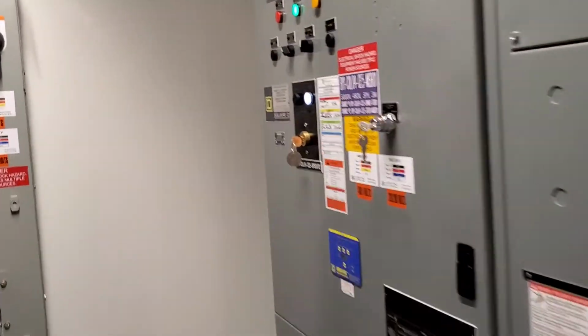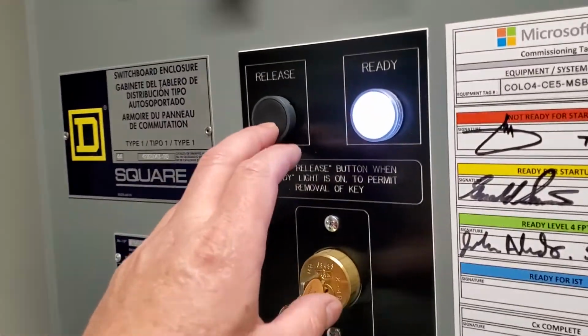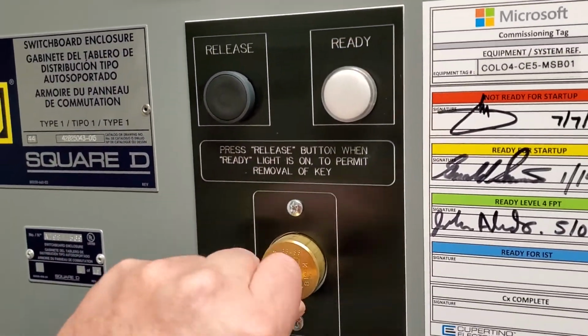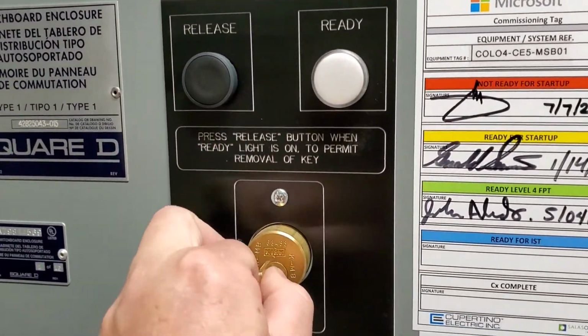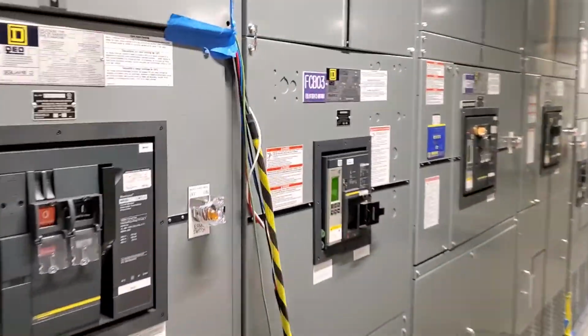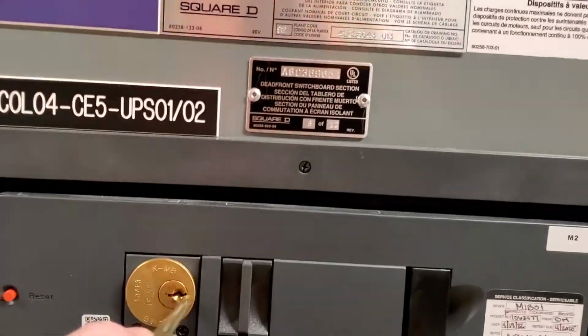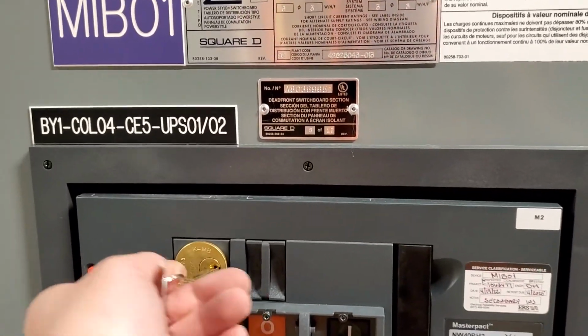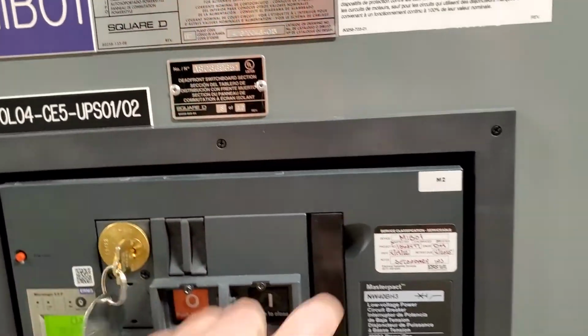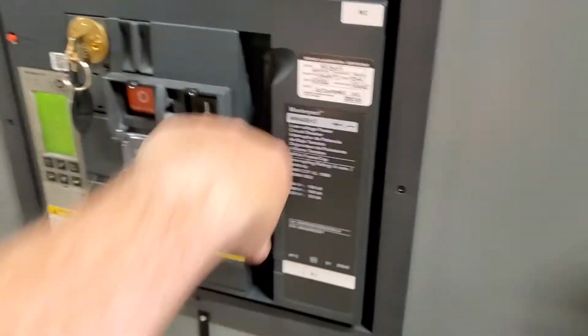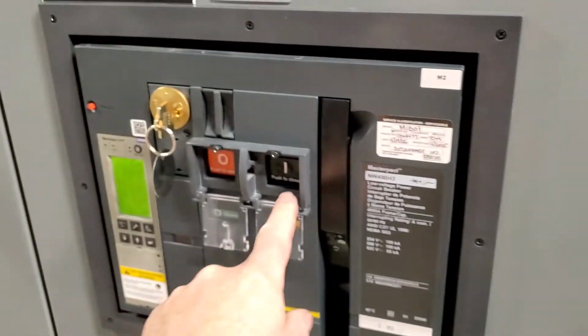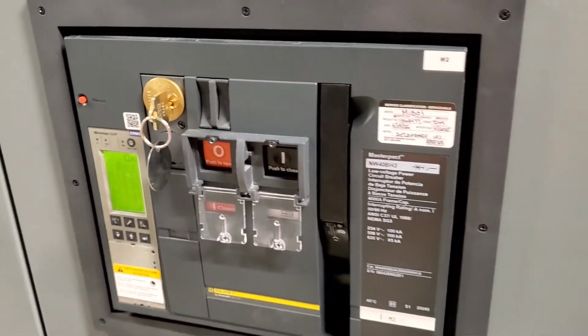So I come over and I see the second Kirk key. I press the release push button and I remove this key. So now I have access to two Kirk keys. One is already in because the MBB breaker is closed. The second breaker, the MIB, needs to be closed so that I can maintain power to the critical bus, as we talked about before. Pumped it up. I'm going to close the breaker. Both MIB and MBB are closed.